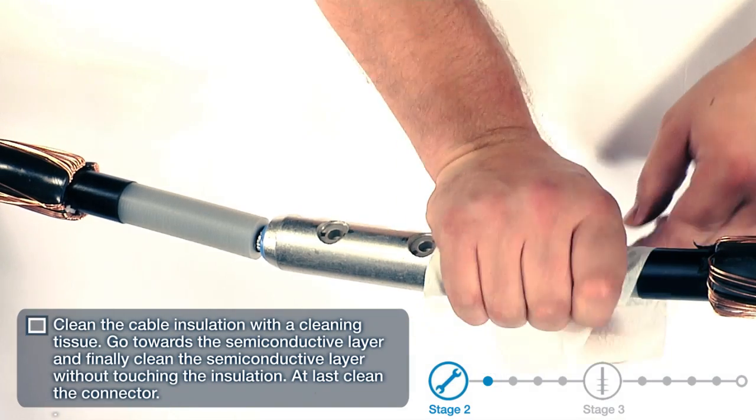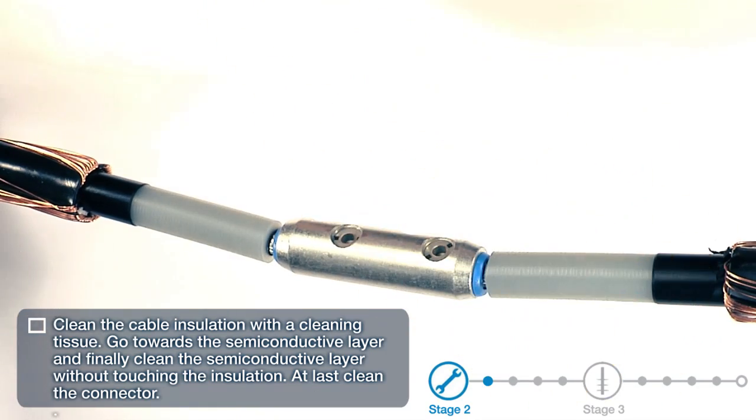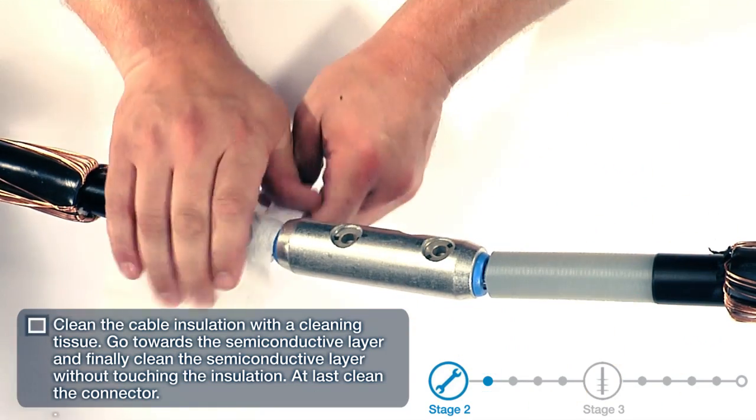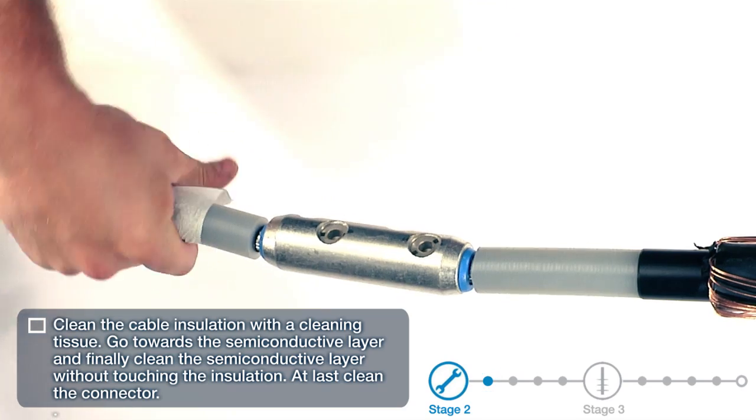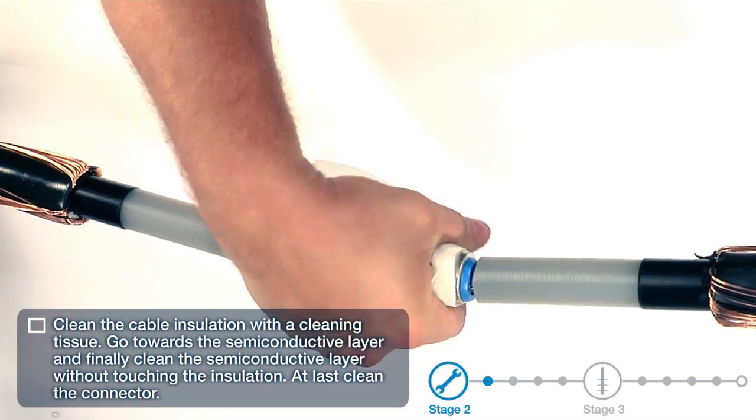Clean the cable insulation with a cleaning tissue. Go towards the semi-conductive layer and finally clean the semi-conductive layer without touching the insulation. Last of all, clean the connector.